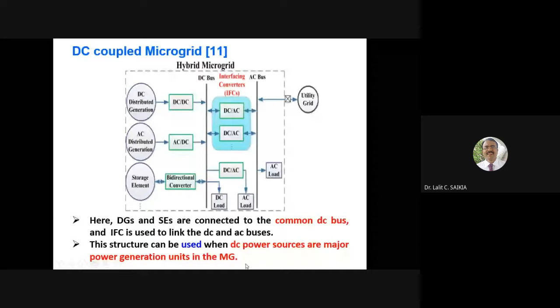This voltage should be fixed - we have to make the AC bus voltage and DC bus voltage fixed at the reference value, so it is required to control the power electronics converter. AC load can be directly supplied from here. DC load can also be directly supplied from this bus, but a converter is required. Here DGs and storage are connected to a common DC bus, and this converter is called an interfacing converter, IFC. Interfacing converters are used to link the AC and DC buses. This structure can be used when DC power sources are the major power generation unit in the microgrid.